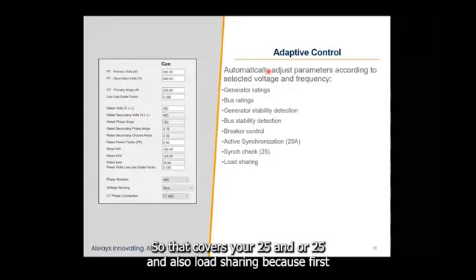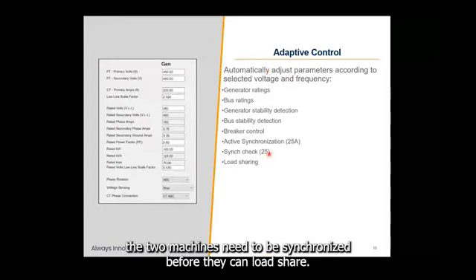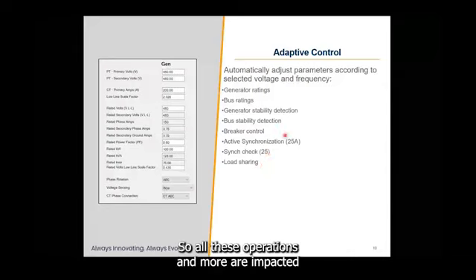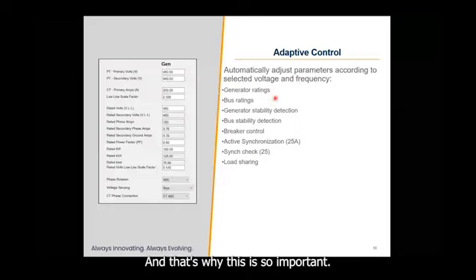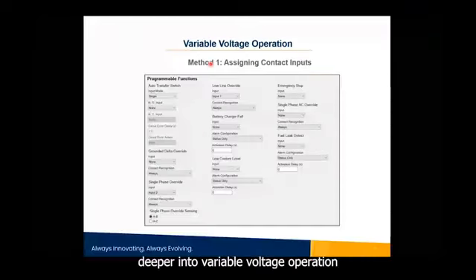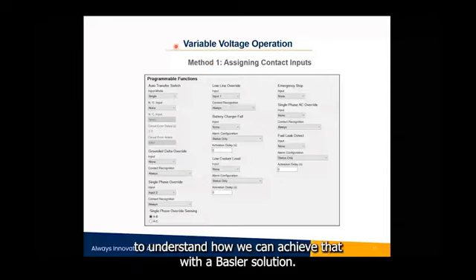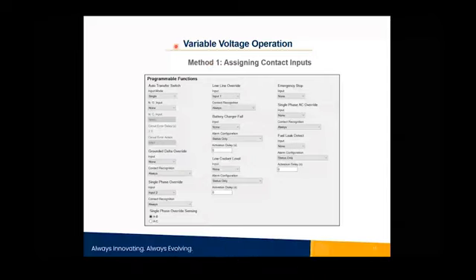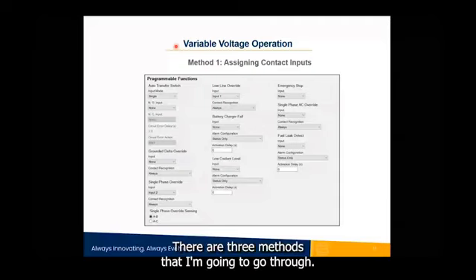So that covers your 25A and your 25, and also load sharing, because first the two machines need to be synchronized before they can load share. So all these operations and more are impacted by the ability of the controller to perform adaptive control, and that's why this is so important. So let's delve a bit deeper into variable voltage operation to understand how we can achieve that with a Basler solution. There are three methods that I'm going to go through.